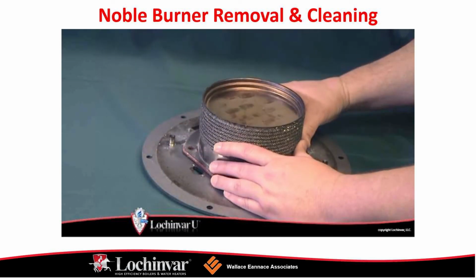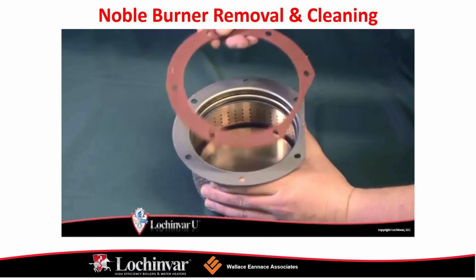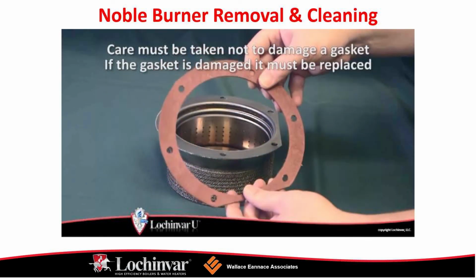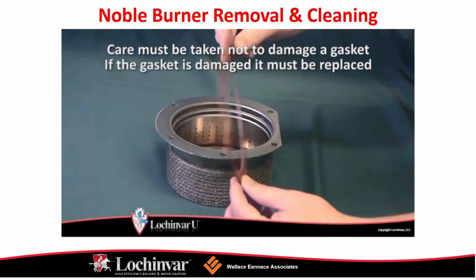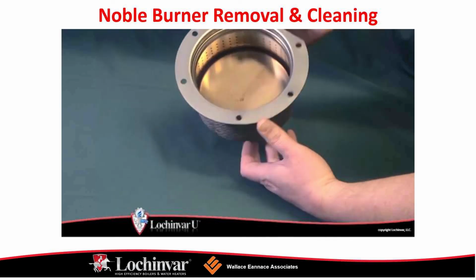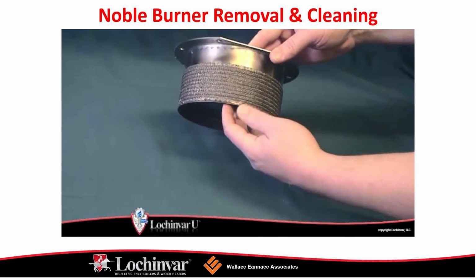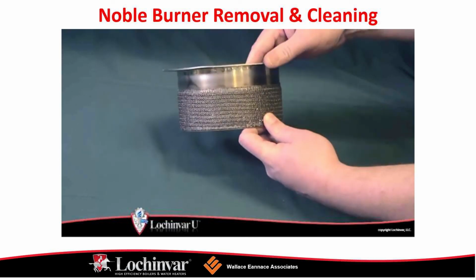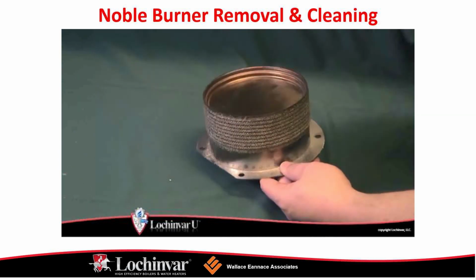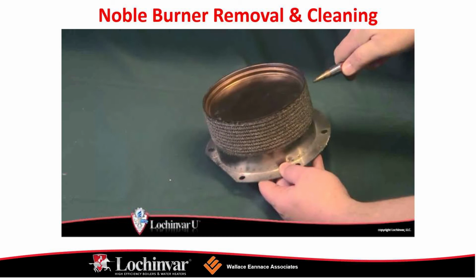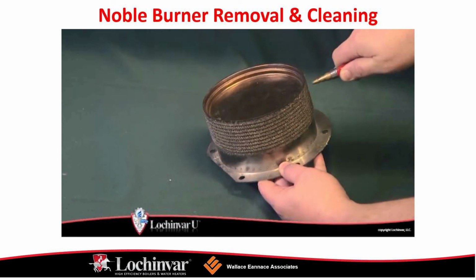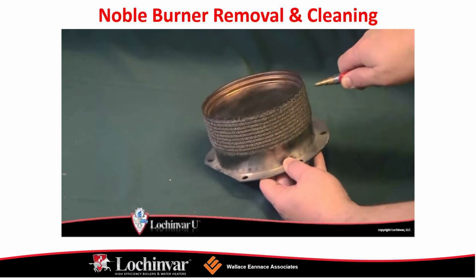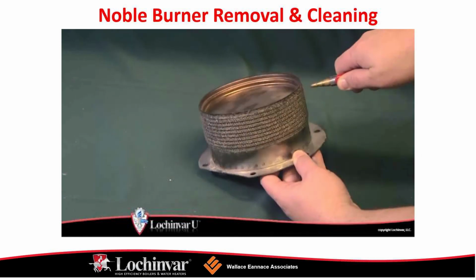Using a 7/16" wrench, loosen the 2 nuts securing the inlet gas pipe bracket to the inlet gas pipe. Then, using a 10mm wrench, remove the nuts that secure the heat exchanger top plate to the heat exchanger. Swing the inlet gas pipe bracket out of the way and remove the heat exchanger top plate. A gasket is used to seal between the heat exchanger top plate and the heat exchanger.